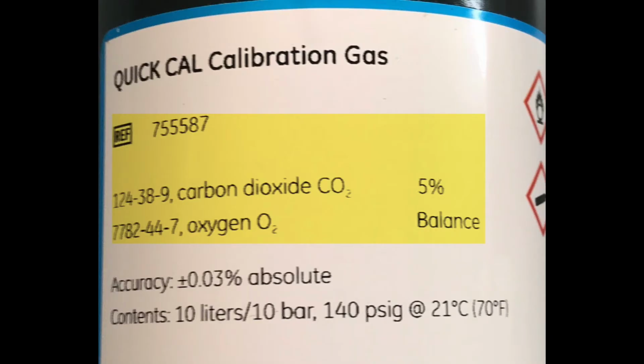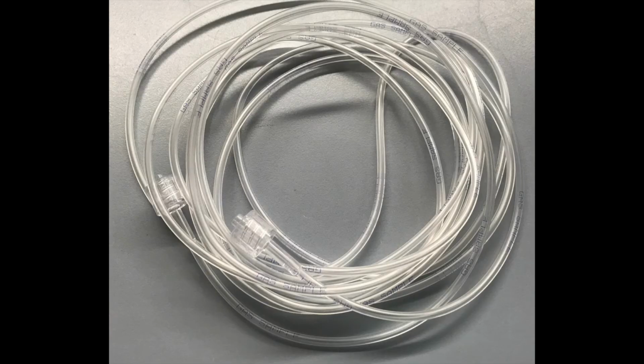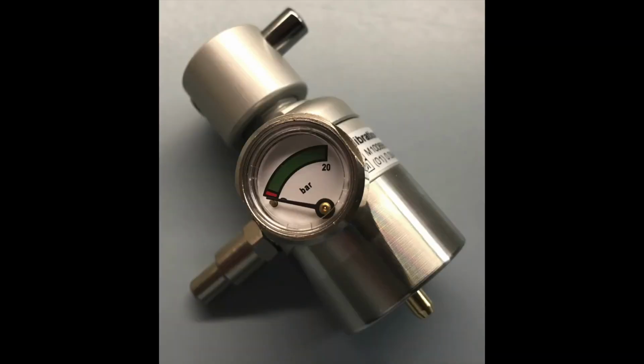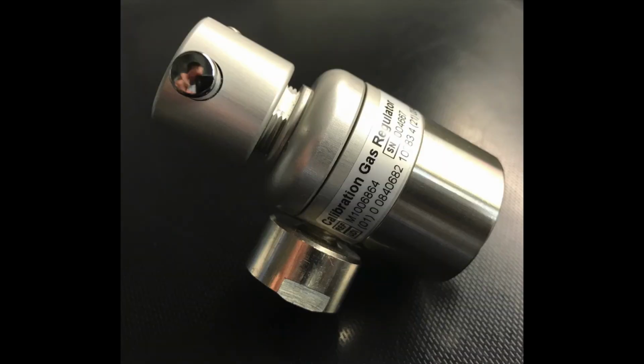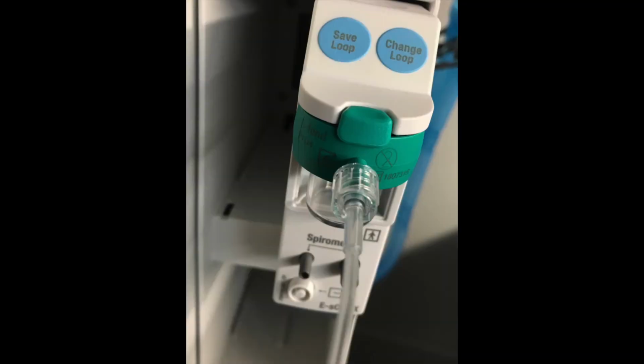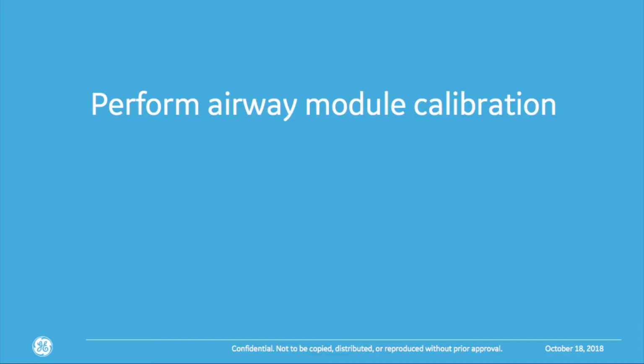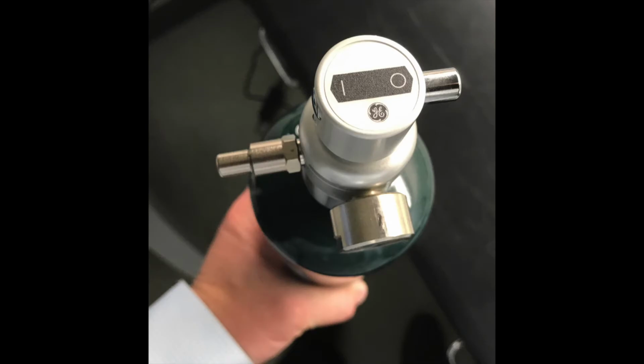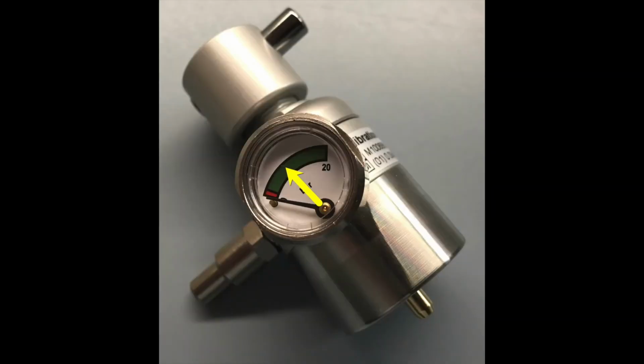And also check the gas mixture. You will also need a gas sampling line, the correct regulator, and of course, the airway module. Attach the regulator to the calibration gas cylinder. Also check the regulator to make sure that there's enough pressure in the tank.